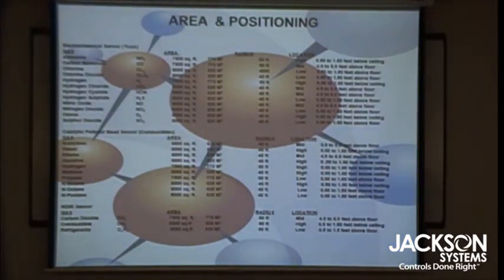There's always a question with NO2. Because NO2 is heavier than air. Traditional thinking thinks, okay, well, we should place it close to the floor. But when you have a fire engine or a dump truck going into a service bay or parking, you have the exhaust stacks pointing to the ceiling. So you can also place the sensor close to the ceiling. Because the gas is warmer, it will detect it quicker than before it sinks down to the ground. And usually roofs of buildings, and those types of buildings are usually warmer than the ground. So it may take a few minutes before that gas reaches the floor. And at that time, you can have a lot of smoke in your garage.